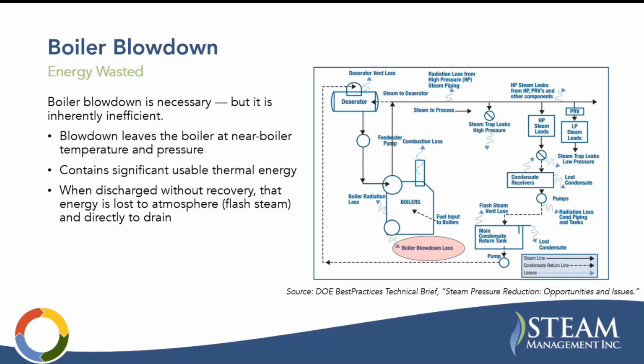The energy wasted here. So what are we talking about? Blowdown is necessary, but it is inherently inefficient. So you're heating up feed water to saturation pressure at the boiler. If you're at a 100-pound boiler, I believe it's like 340 degrees or so. So you're heating water up all the way to that temperature, and then you're just rejecting it and blowing it down the drain. So there's a significant amount of thermal energy there.